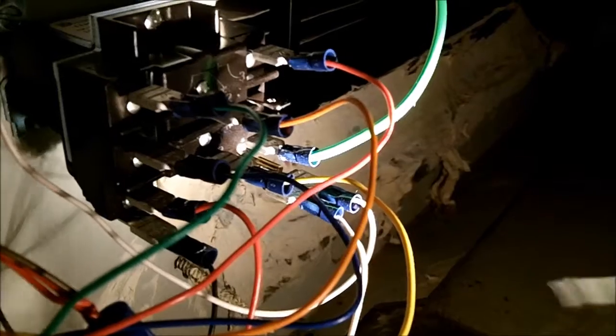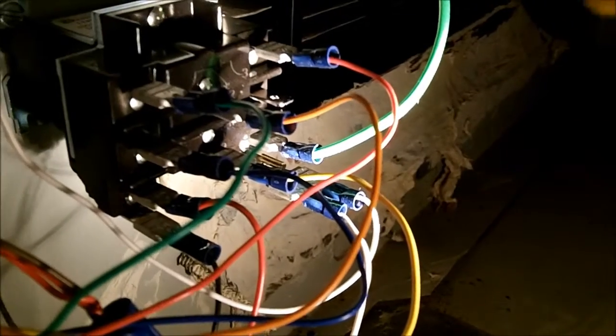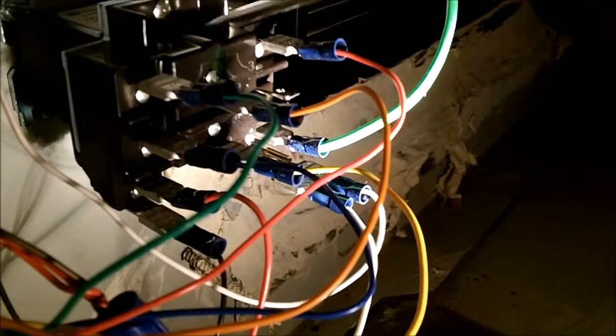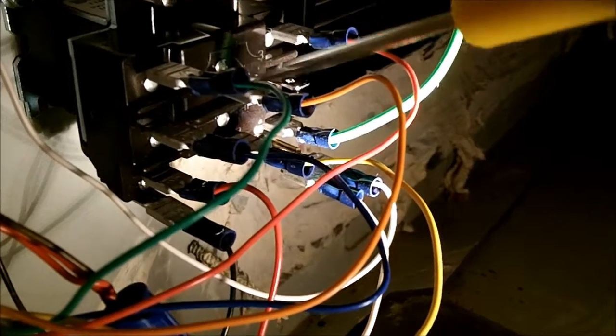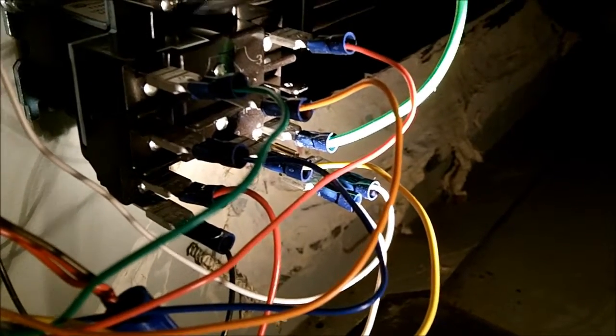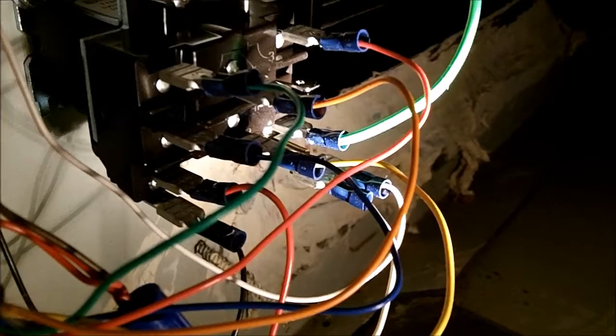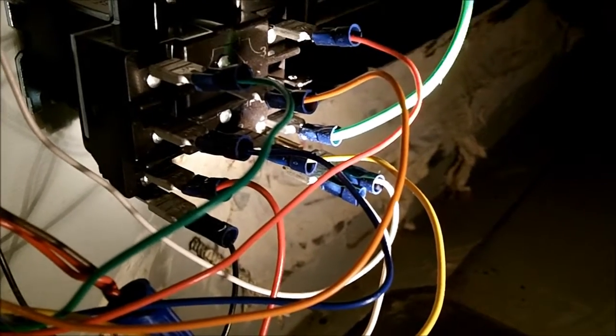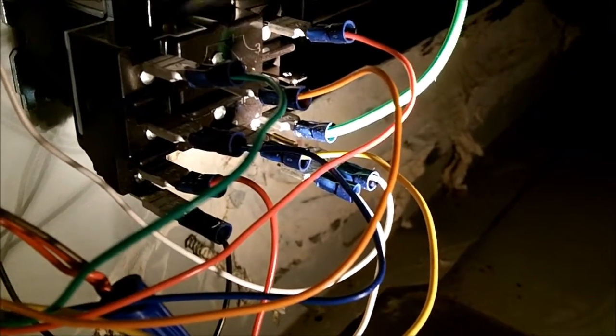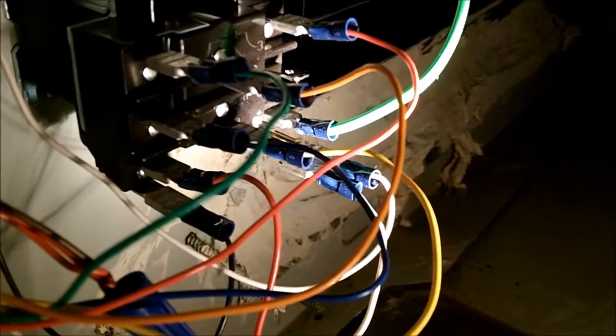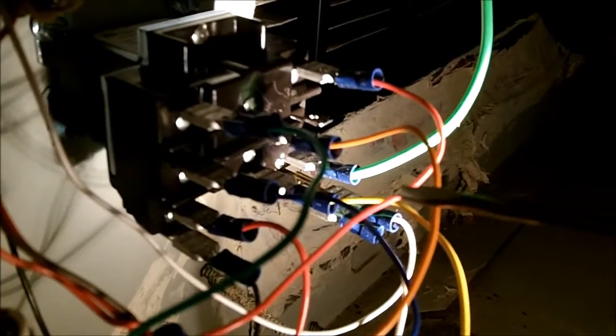The orange wire here comes from the thermostat. So when the coil is de-energized, this contact here and here will be closed, because it's a normally open, normally closed relay. This is your normally closed circuit, normally open from here to here. So if they turn the fan to the on position on the thermostat, it's going to send power to here, sending power to here, going up and feeding the circuit board.